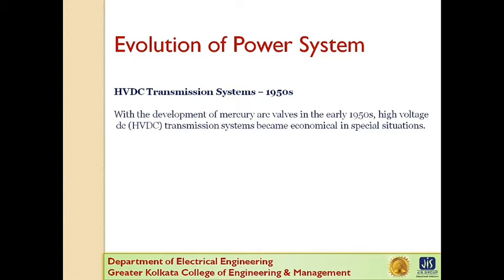The first modern commercial application of HVDC transmission occurred in 1954, when the Swedish mainland and the island of Gotland were interconnected by a 96 km submarine cable. With the advent of the thyristor valve converter, HVDC transmission became even more attractive. The first application of an HVDC system using thyristor valves was Eel River in 1972, a back-to-back scheme providing an asynchronous tie between the power systems of Quebec and New Brunswick. With the cost and size of conversion equipment decreasing and its reliability increasing, there has been a steady increase in the use of HVDC transmission.